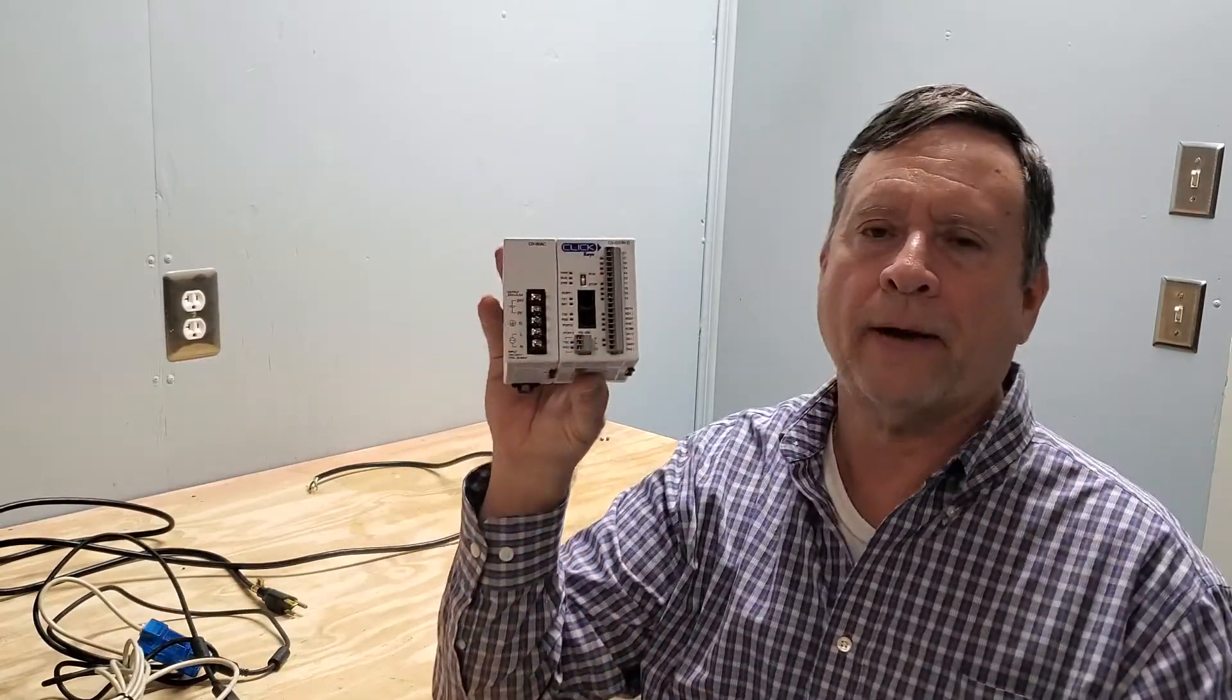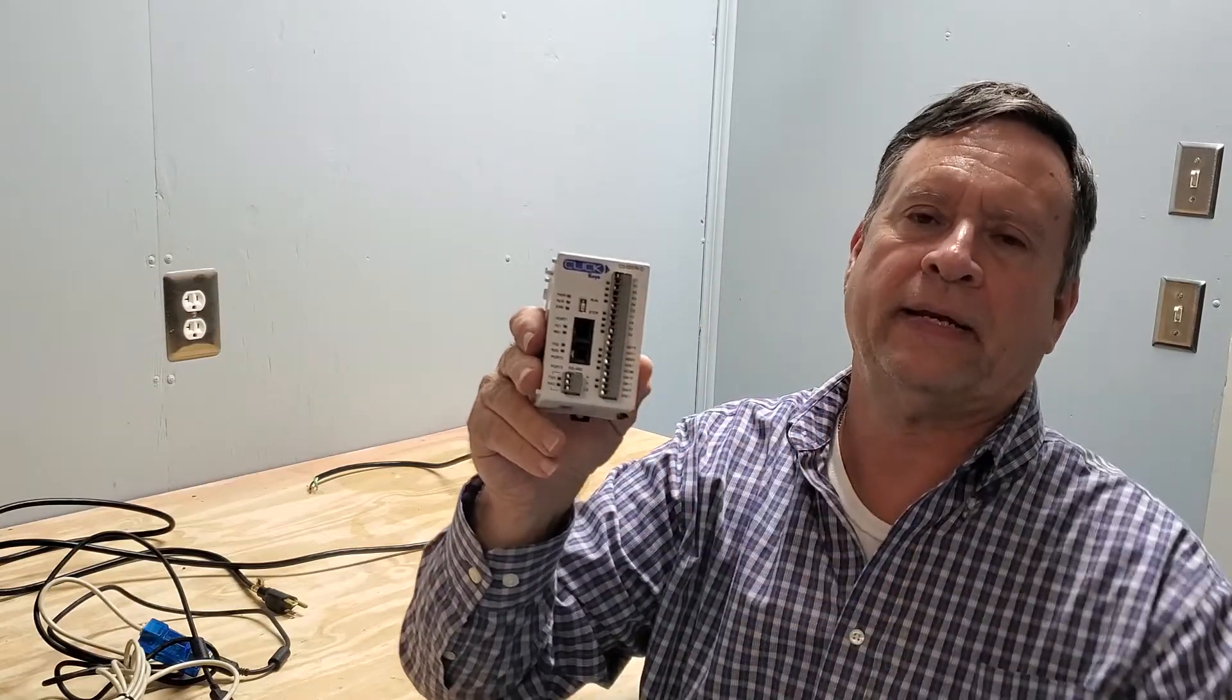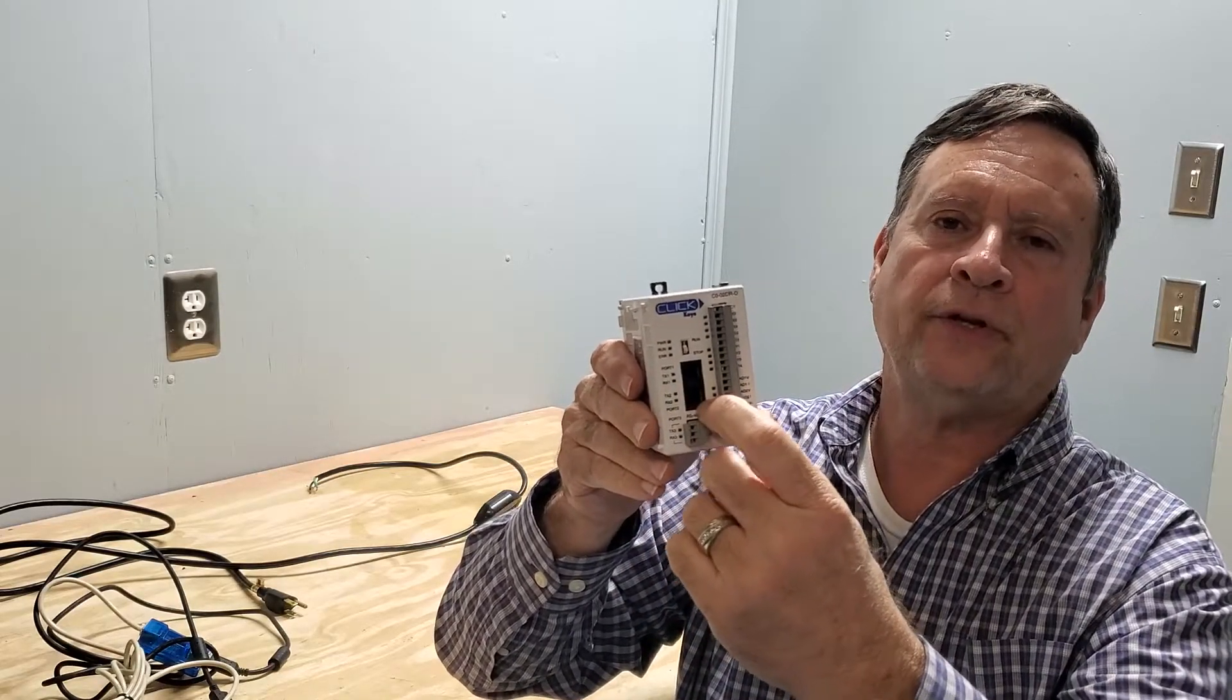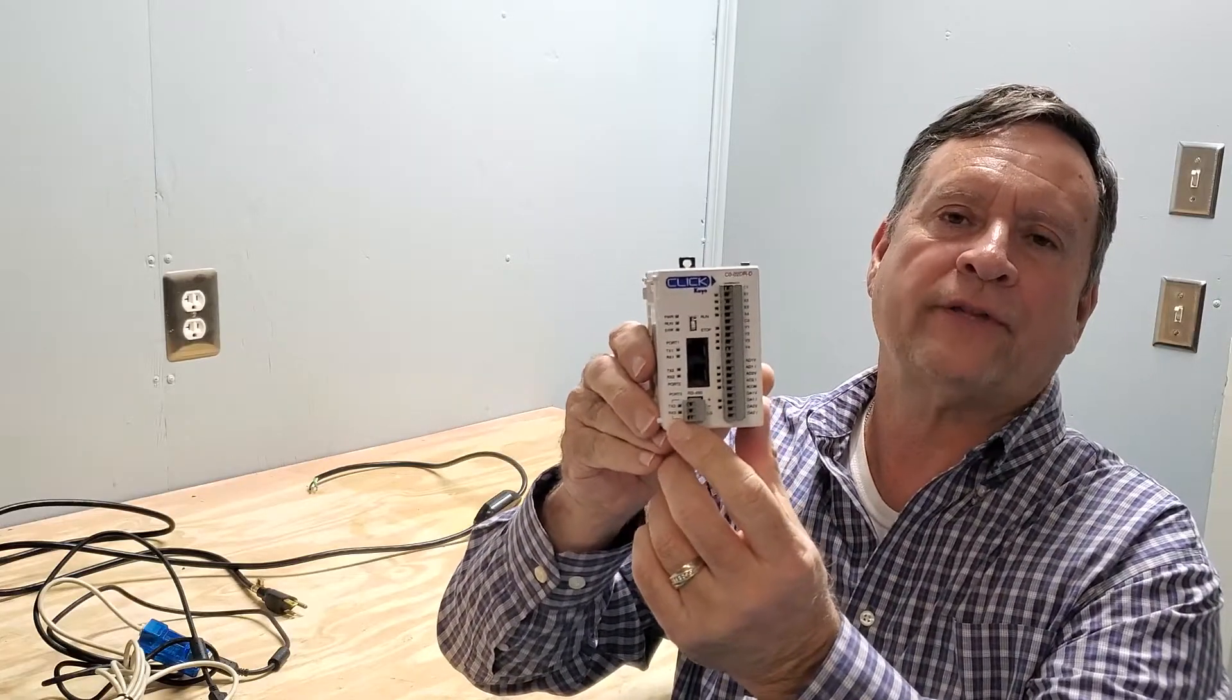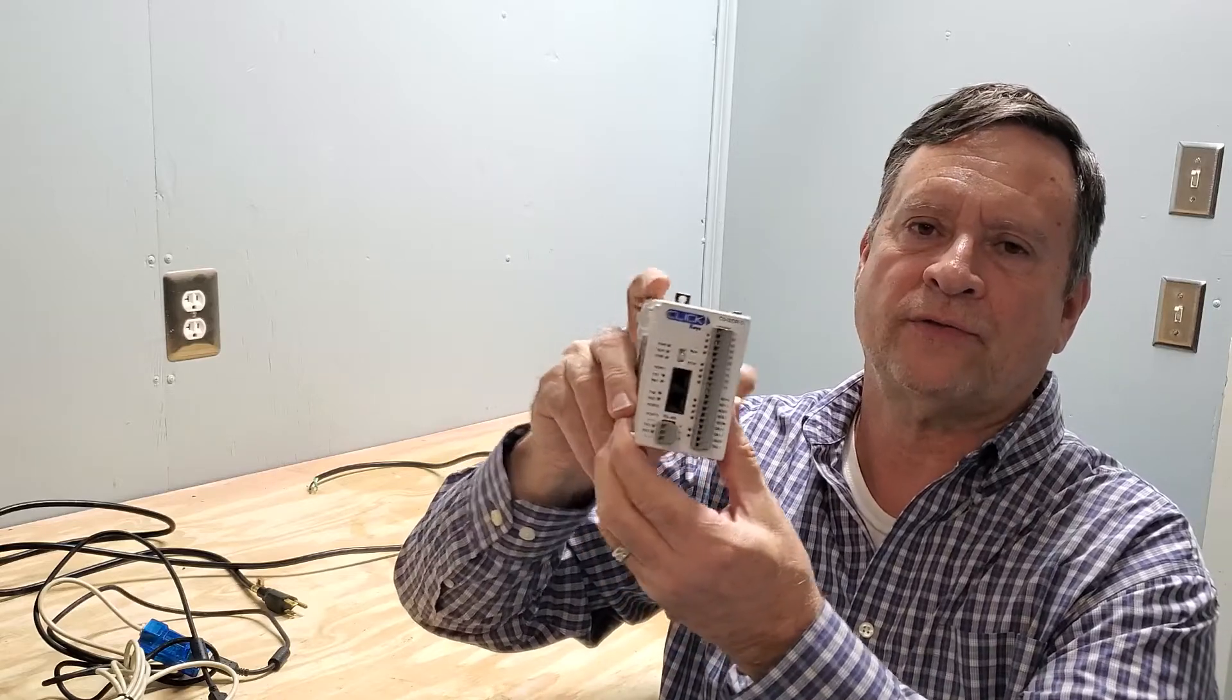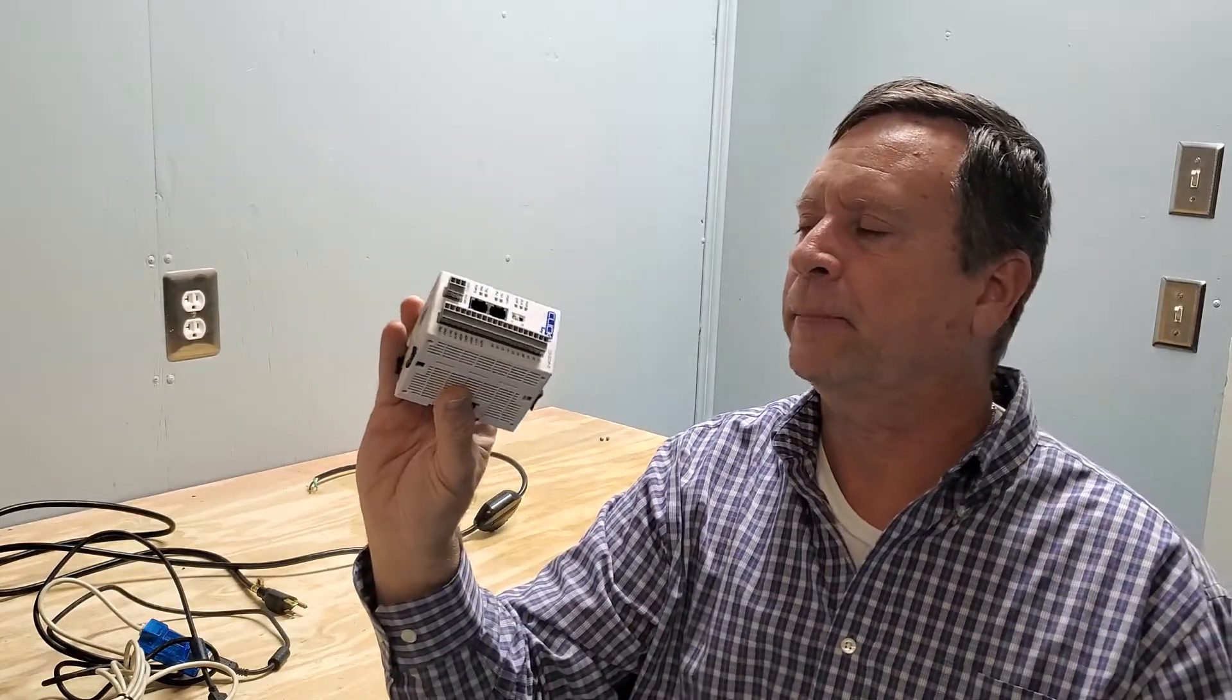Now this is considered a micro brick. They call it a brick because of the physical shape, and that's an industry standard term for this type of PLC, a small PLC that has fixed inputs and outputs already on it. This one has an RS-232 port for typically the programming port. It has the second RS-232 port for connecting to another device such as an HMI, a display panel, a touch screen. It also has another port, an RS-485 port which runs the Modbus protocol, which can connect up to another I think 62 other devices, which can be AC drives, they can be other PLCs, they can be radio communications from one PLC to another. It can be a hard wire connection for a string of different products. So it's very powerful.